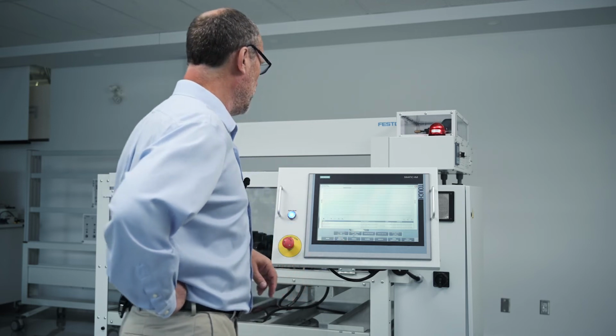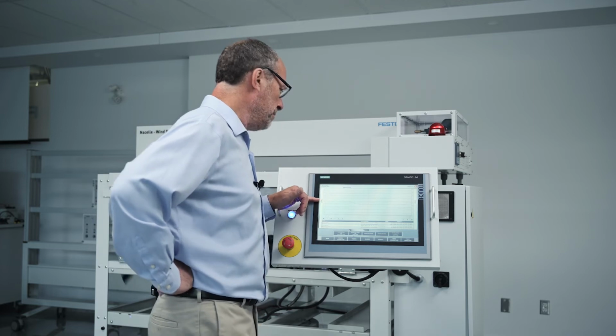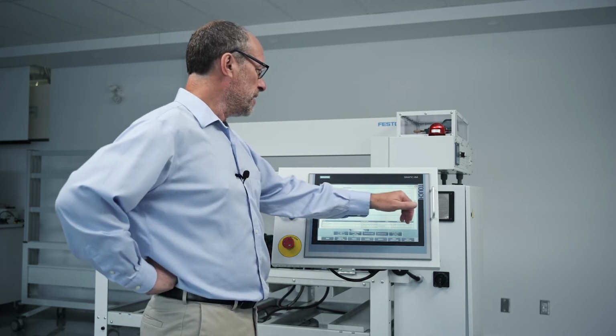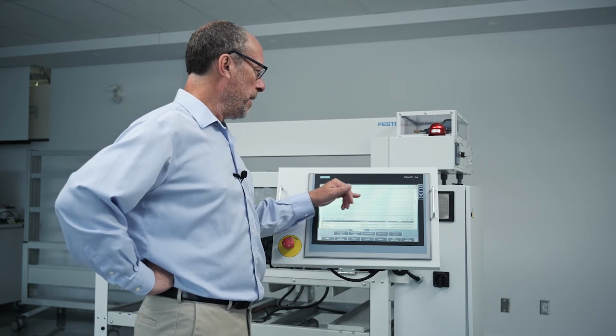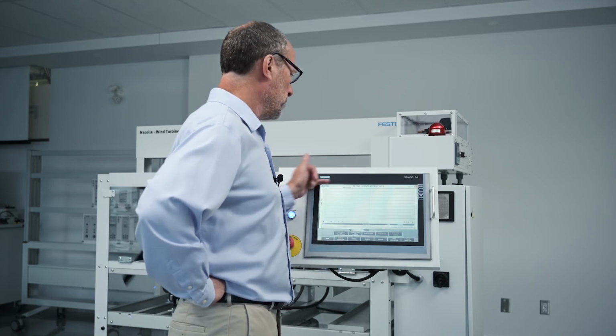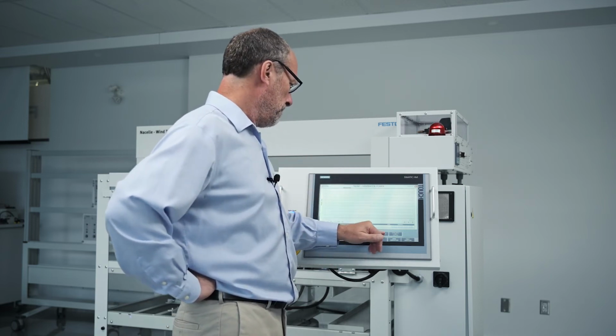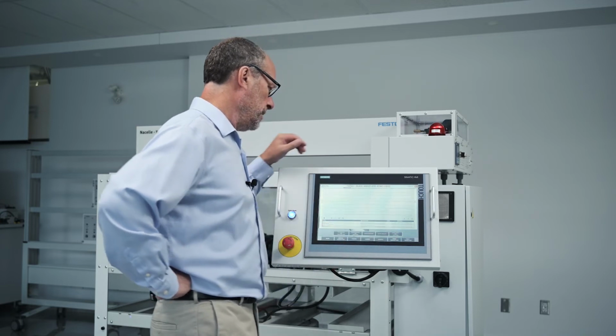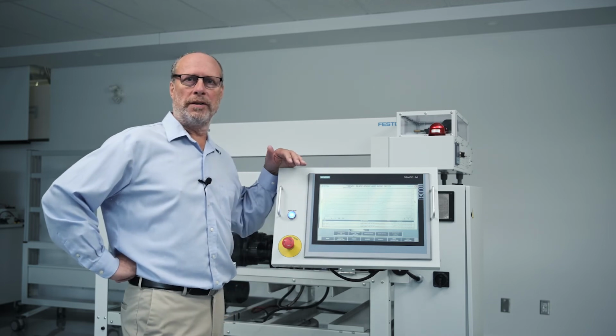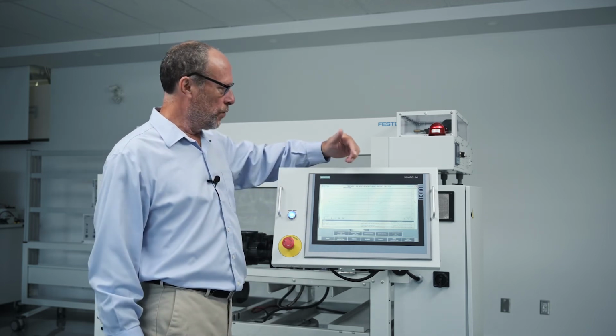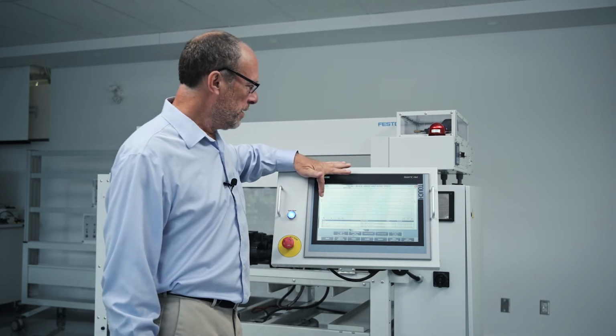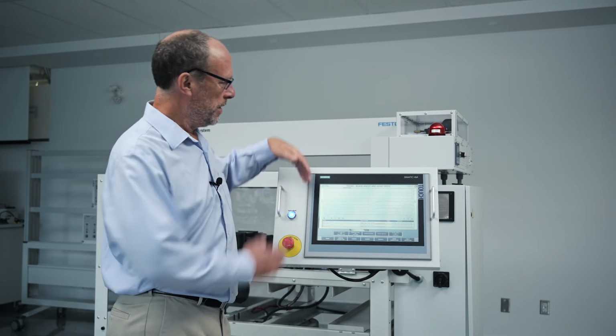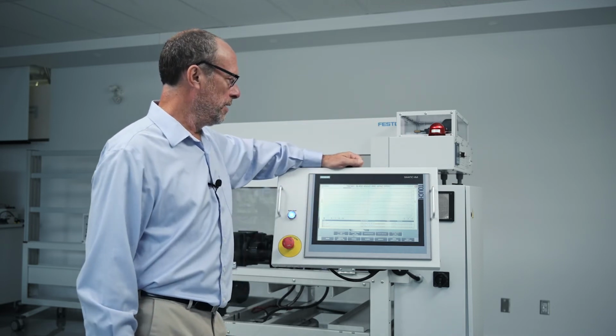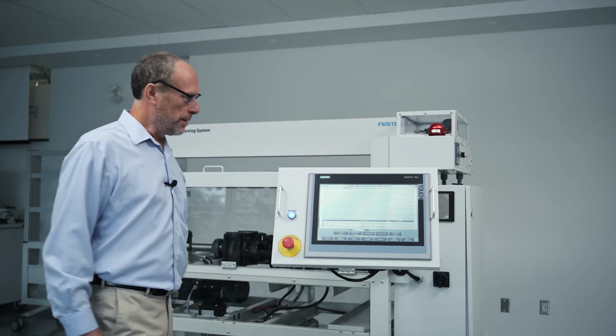If I change to the next screen, in this case, this is the RPM of the machine, which is maintained, and this is the wind speed. So you can see that we maintain the speed while the wind speed is changing. Power, it's 100%. Well, the line is at top here. Here you can see the simulated blade angle. So on the hub, you have angles that change according to the wind. So here you have the wind speed and the blade angle. So they should follow approximately the same look.